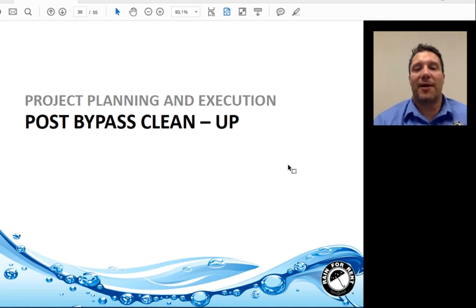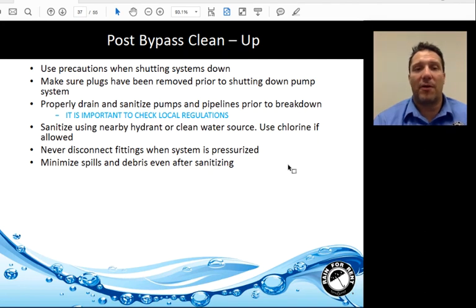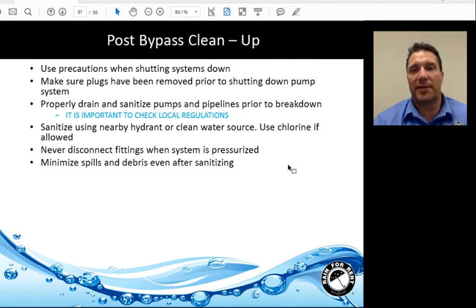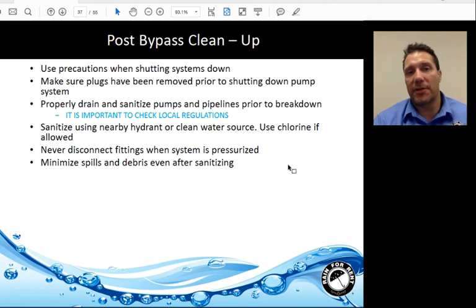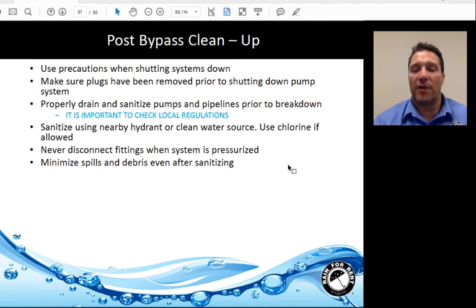Post-bypass cleanup: Make sure the plugs have been removed prior to shutting down the pumps. Properly drain and sanitize the pumps and pipelines prior to breakdown, keeping in mind what regulations govern your project — for example, whether chlorine can be used or discharged directly into the manholes. Check pressure readings on the system to ensure everything has been properly depressurized before equipment is broken down.